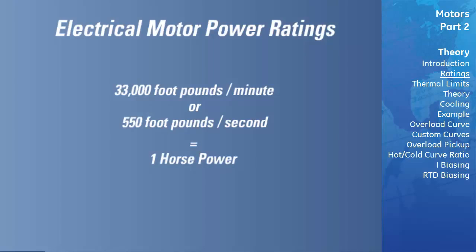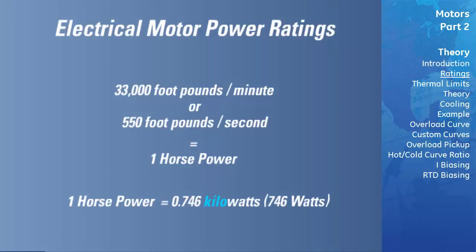Horsepower has remained as a standard unit of power rating for electrical motors in North America, while in Europe the kilowatt has become the standard. One horsepower is equal to 746 watts, or 0.746 kilowatts. To convert a motor's kilowatt rating to horsepower, one can simply multiply the kilowatt rating by 1.341.